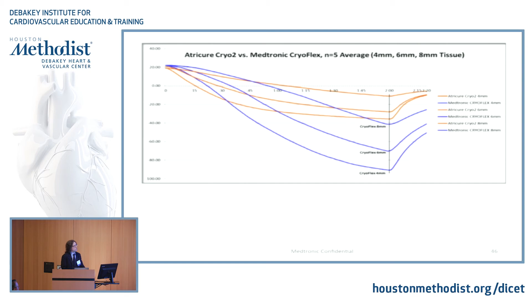This is for the 4 millimeter tissue, and we had 8 temp probes along the probe, because when you read -60, it's only at one point. It's not in the tissue, which is maybe more important. And as you can see, it changes between the different thicknesses of the tissue, although it's not as important when it comes to the Medtronic one because it's always below the temperature that is the killing temperature. This is a tissue temperature, as I said, but it may be important when it comes to the Cryo 2.